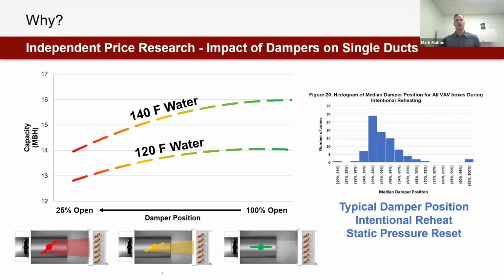It kind of is when my wheels started churning, and we started to do some independent testing at Price facilities, trying to further quantify and understand what is the impact of a damper on a single duct reheat coil. And what we found was very similar findings, up to a 15% degradation in capacity when a damper becomes too closed. And the problem here is we could use static pressure reset, so essentially turning down the air handler to make dampers more open to rectify and overcome some of these constraints.